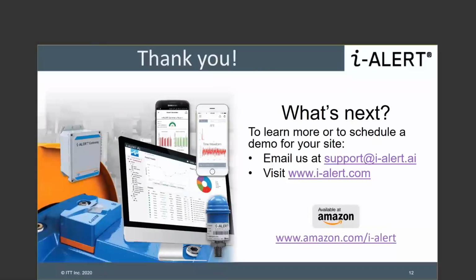Just a follow-up question. You mentioned the gateway. Someone had a question of how many of the sensors can one gateway support? We've tested them in our lab, and Naveen, I think you can support me on this, we've tested up to about 264 on a single gateway. It doesn't seem to slow things down at all. That would be an unusual case where you have that many iAlerts that close. A more typical installation would be 50 to 100, say on a paper machine or something.